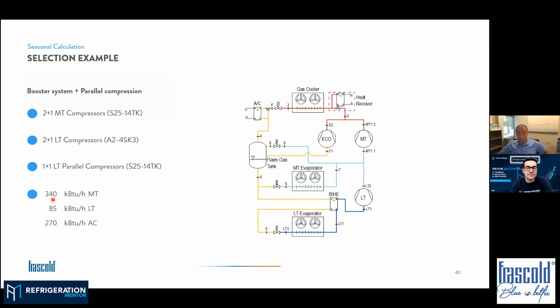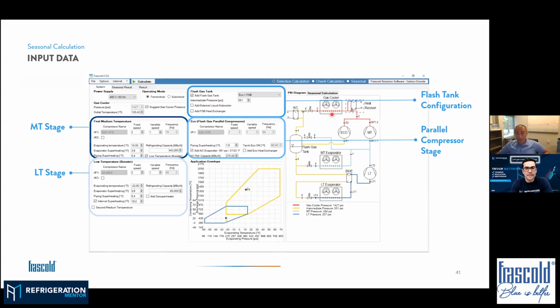So we selected 340 kBtu per hour at medium temp, 85 for low temp, and then we added some air conditioning, 270 kBtu on the air conditioning side. The software may look complicated at first sight, but it's a selection tool, first of all, so we can select our configuration - this is a booster system with parallel compression and air conditioning.